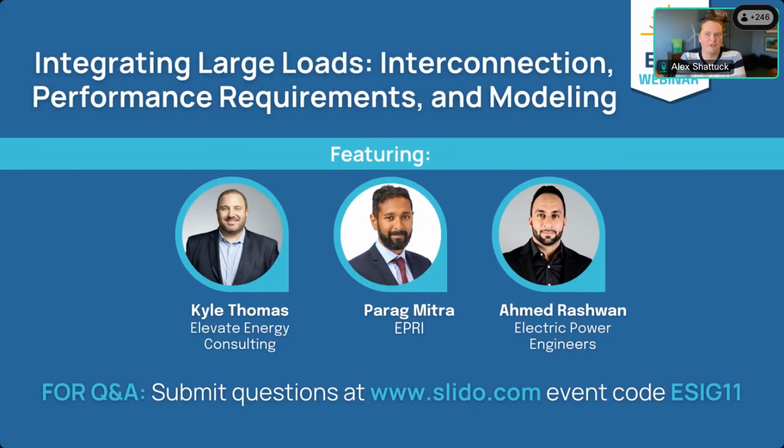The only additional thing I would add is, Ahmed just answered in relation to some of the more unique characteristics of the large loads. But that's not to say that those are the only considerations for modeling the large loads. A lot of the same considerations and best practices that we are presenting here at ESIG, and in the NERC dynamic modeling recommendations and that type of guidance, all of that will still apply to these large loads. Those are technology specific, vendor specific models with site specific parameters as much as you can.